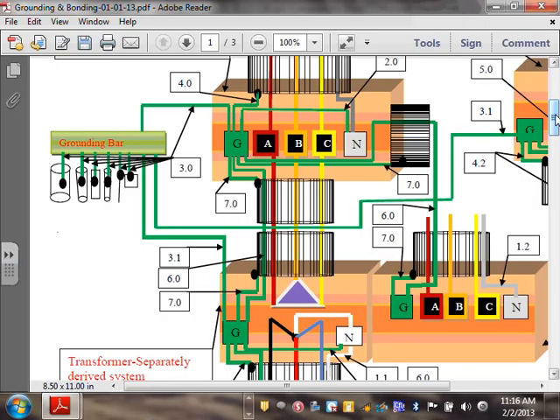So one of the most important things about bonding the neutral to the ground is stabilizing the neutral to the ground. Upon the loss of the neutral, in this case you're highly unlikely to lose it here, but at the service, if you lose it, now the ground will act as your neutral back to the service. At least you don't burn equipment. It's not recognized as a return path, but it's enough to not burn equipment.